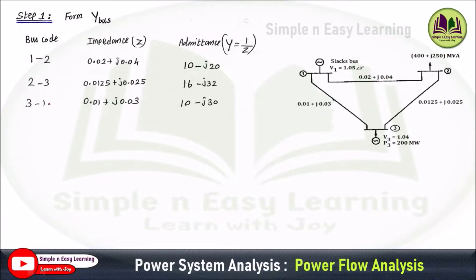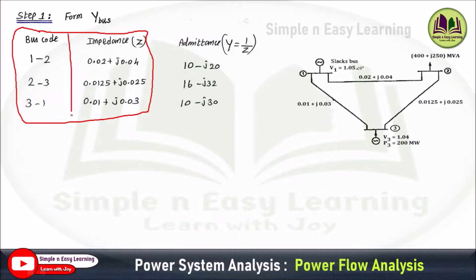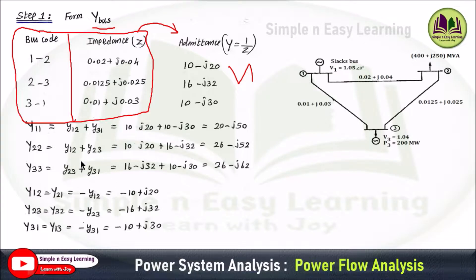Step 1: form the Y bus. The bus code and impedance in per unit are specified in the problem. We form the admittance matrix by converting impedance to admittance using Y equals 1 divided by Z. You will get the admittance values. Now form the Y bus matrix with diagonal and off-diagonal elements. Y11 equals the sum of admittances of lines connected to bus 1, that is Y12 and Y13 added together, giving 20 minus J50.